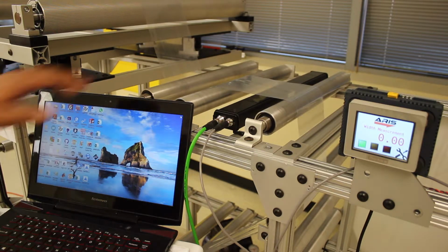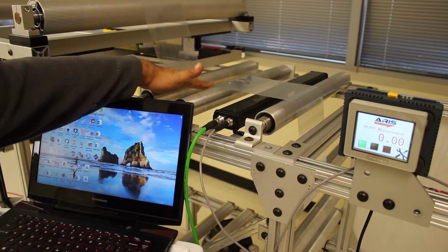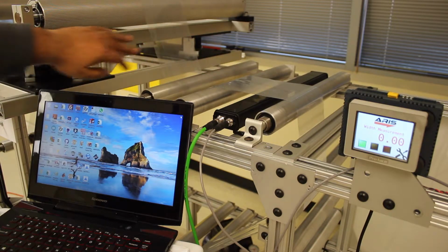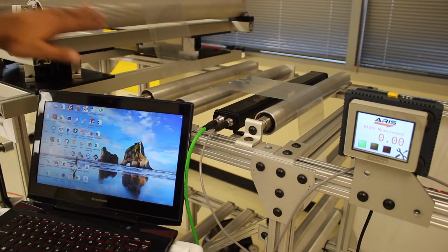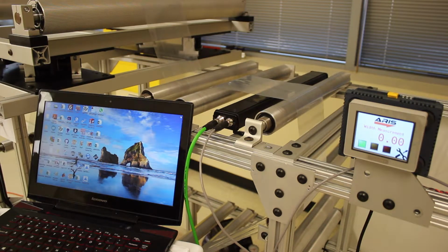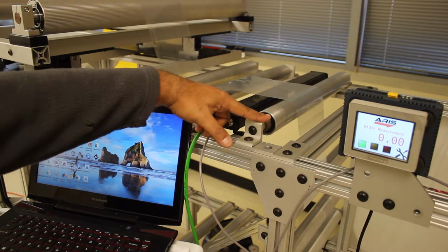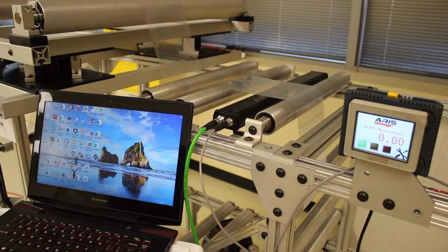Other things to consider is that this free span doesn't have any twisting. So we don't want to install the sensor right next to a dancer roller or right next to a web guide. We want to install the sensor between two fixed rollers so that we have a fixed span and the web doesn't flutter. That will be the ideal scenario.